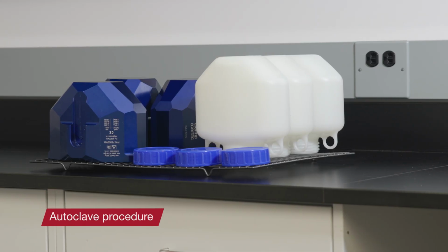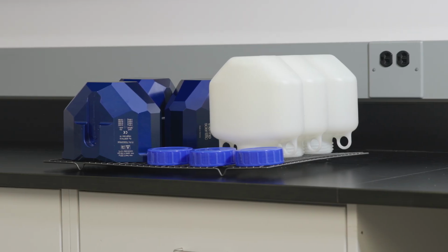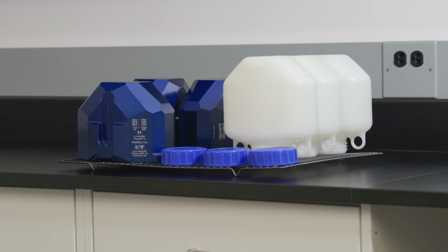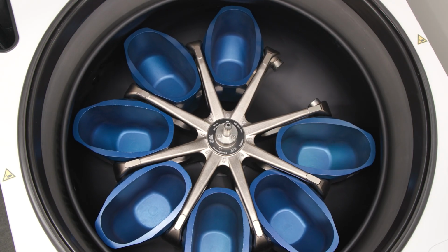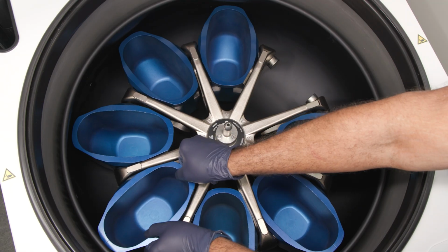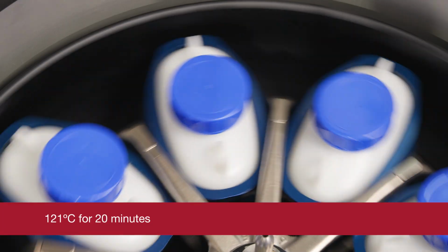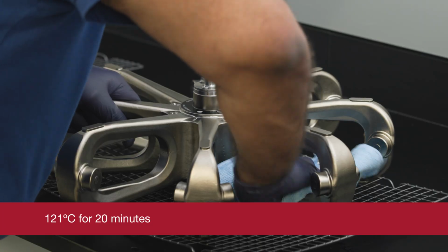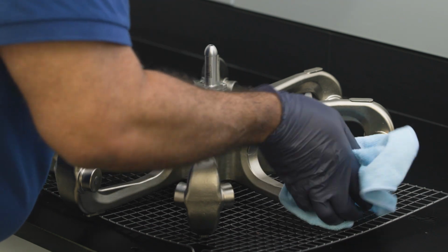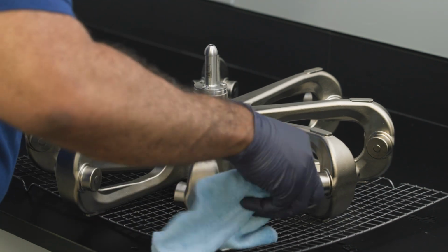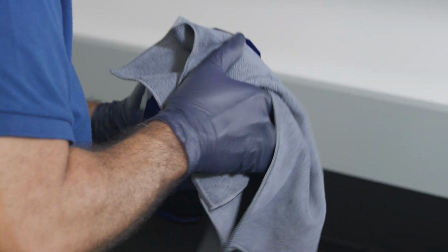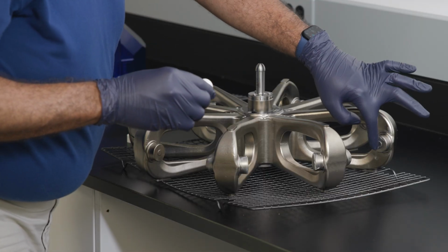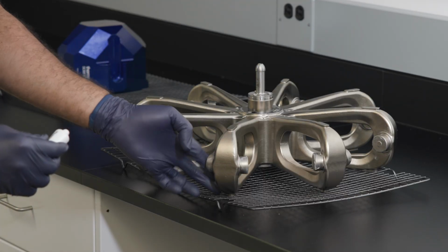To autoclave the components, separate the rotor, buckets, lids, adapters, tubes, and sealing rings for thorough cleaning. Remove lids from rotors, buckets, and tubes if installed. Then autoclave the marked components at 121 degrees Celsius for 20 minutes. No chemical additives are allowed in the steam, and you should never exceed the permitted temperature or duration when autoclaving. After autoclaving, treat aluminum parts and their cavities with corrosion protection oil, and treat the bolts of the swing-out rotor with bolt grease once more.